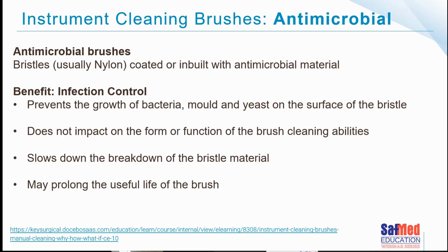It doesn't make it a better cleaning brush. But what it does do is prevent the growth of bacteria, mold, and yeast on the surfaces of the bristle, which of course is going to be an advantage. If you haven't cleaned off the patient debris, though, it's not really going to help you much because there's so much patient debris. But hopefully it can prevent the growth of mold and yeast if you're managing the bristles correctly. The advantage of these antimicrobial materials in brushes is that it slows down the breakdown of the bristle material, which hopefully can prolong the useful life of that particular brush.